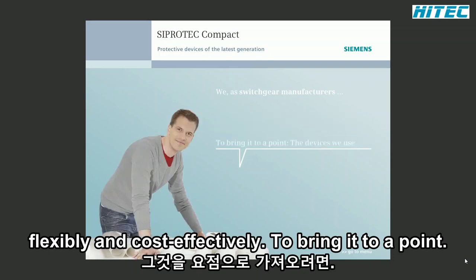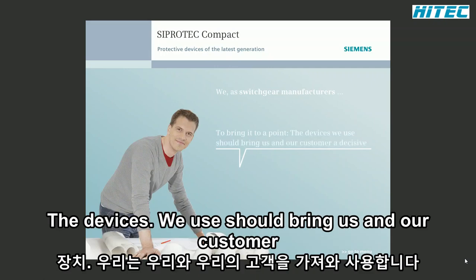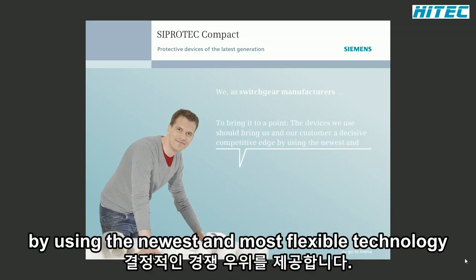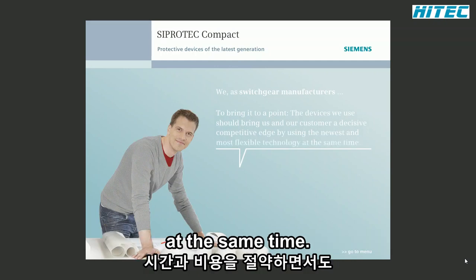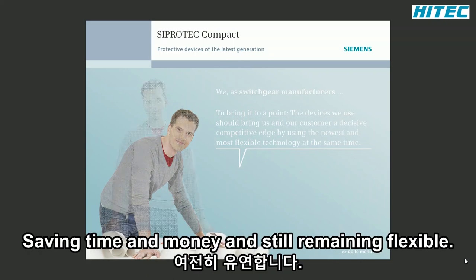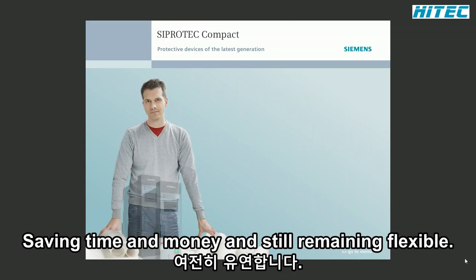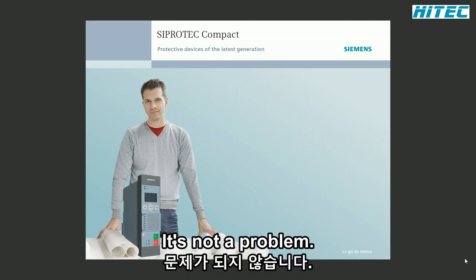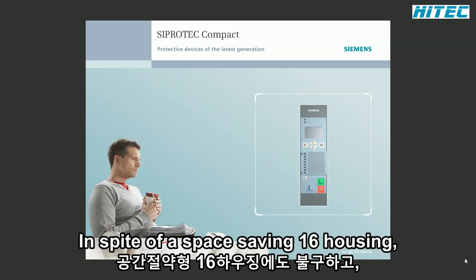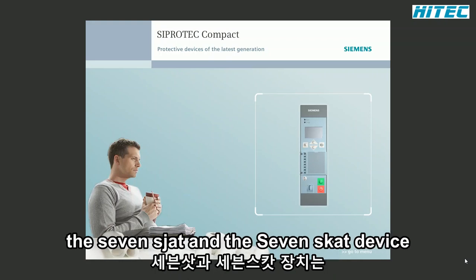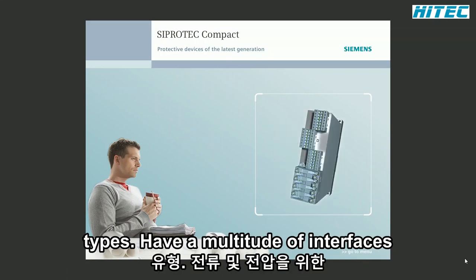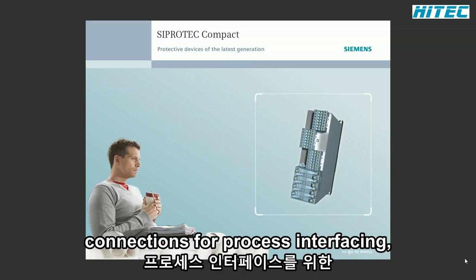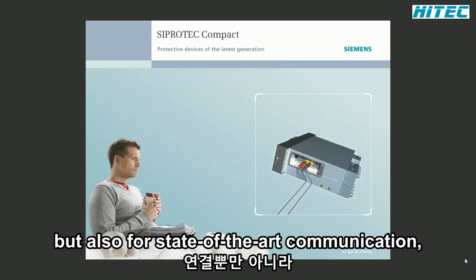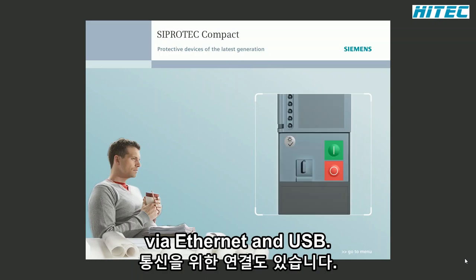To bring it to a point, the devices we use should bring us and our customer a decisive competitive edge by using the newest and most flexible technology at the same time. Saving time and money and still remaining flexible, with SIPROTEC Compact it's not a problem. In spite of a space-saving 1/6 housing, the 7SJ80 and the 7SK80 device types have a multitude of interfaces for current and voltage connections, for process interfacing, but also for state-of-the-art communication, for example via Ethernet and USB.